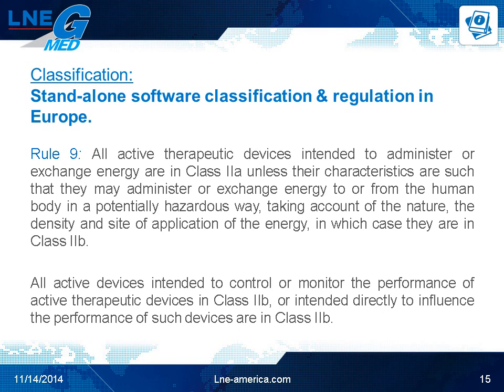Rule 9 states that all active therapeutic devices intended to administer or exchange energy are in Class 2A, unless their characteristics are such that they may administer or exchange energy to or from the human body in a potentially hazardous way — taking account of the nature, density, and site of application of the energy — in which case they are in Class 2B. All active devices intended to control or monitor the performance of Class 2B active therapeutic devices, or intended directly to influence their performance, are also in Class 2B. Examples include radiotherapy planning systems used to calculate the dose of ionizing radiation to be administered to a patient, or insulin dosage planning standalone software.